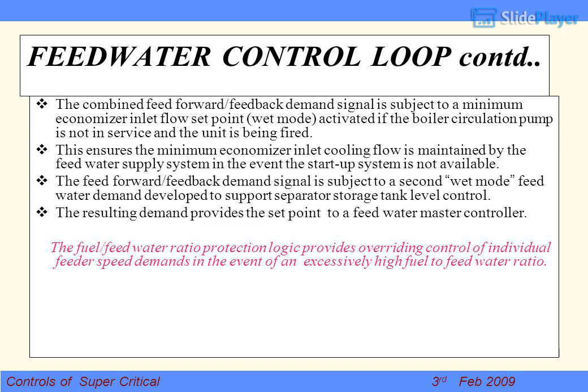The feed forward/feedback demand signal is subject to a second wet mode feed water demand, developed to support separator storage tank level control. The resulting demand provides the set point to a feed water master controller. The fuel-to-feed water ratio protection logic provides overriding control of individual feeder speed demands in the event of an excessively high fuel-to-feed water ratio.